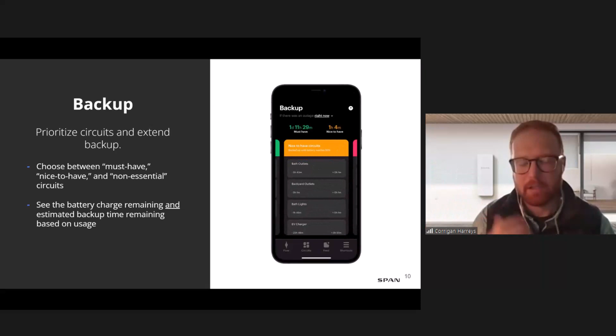Something you're probably all interested in, as the EV Club of Connecticut: SPAN and EV chargers. If you have a SPAN panel, whether it's a Tesla wall connector, a juice box charger, or a SPAN EV charger, you can get a full level 2 charge. Today, to get a full level 2 charge you'd need a 60 amp breaker for your 48 amp level 2 car charger. If you have 100 or 200 amp service, you may not have room for that full 60 amp breaker, meaning you've invested a high dollar value in your EV but have to derate your charger or use a 120 volt plug-in, which can take up to 3 days to charge your car—not the experience you want after investing in your EV.